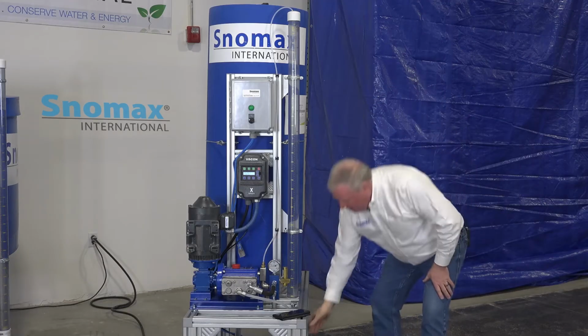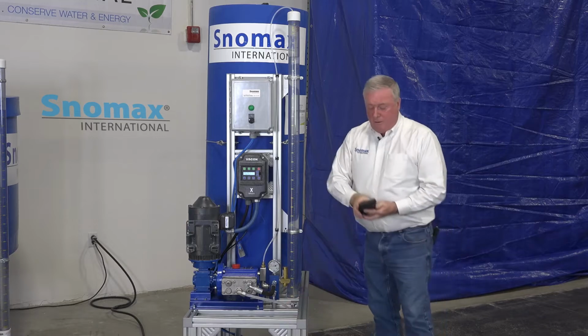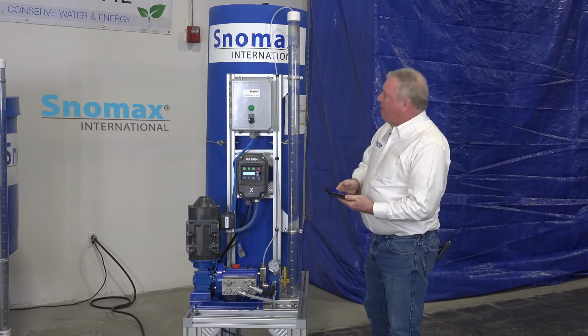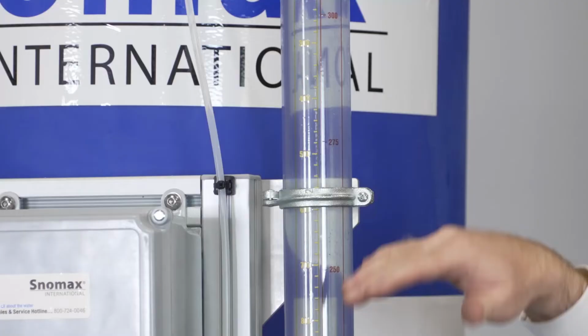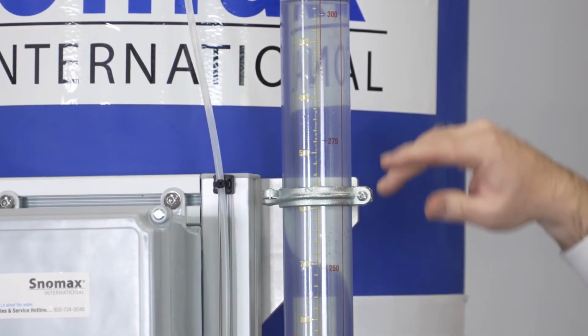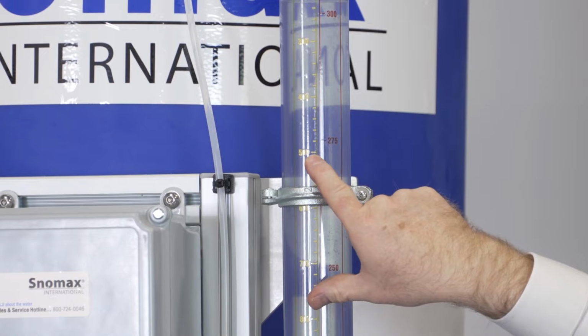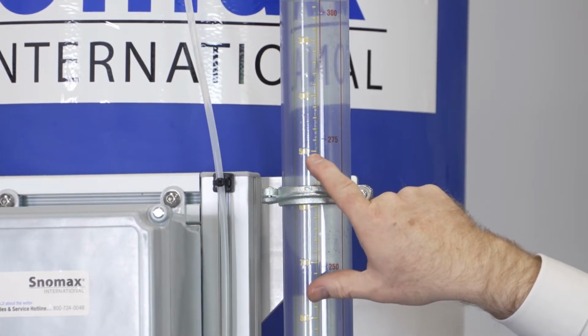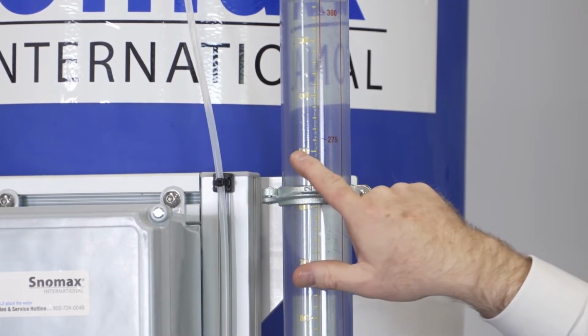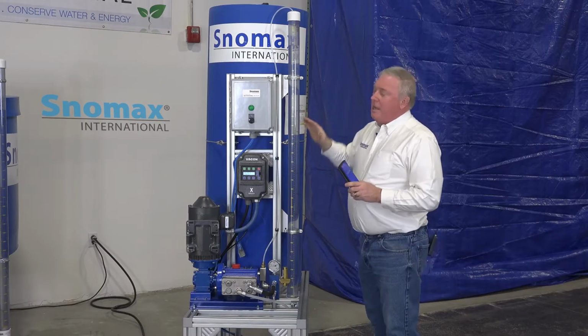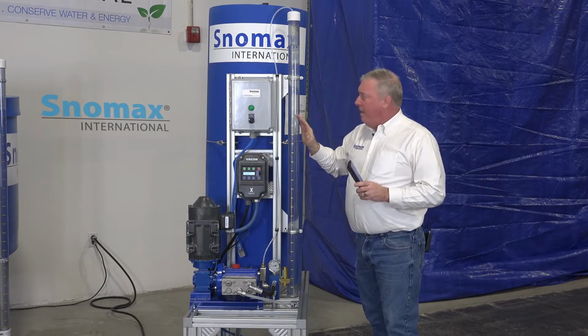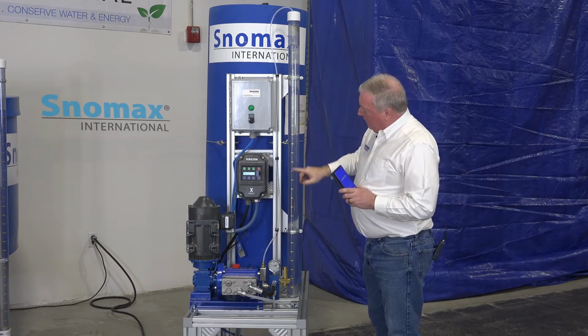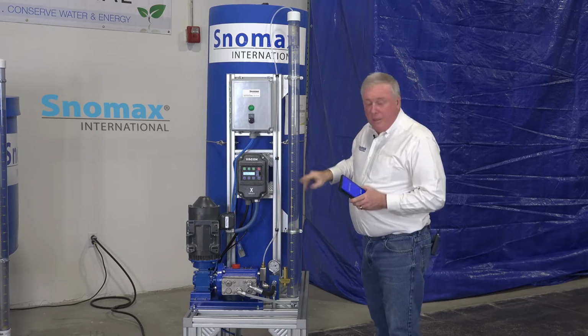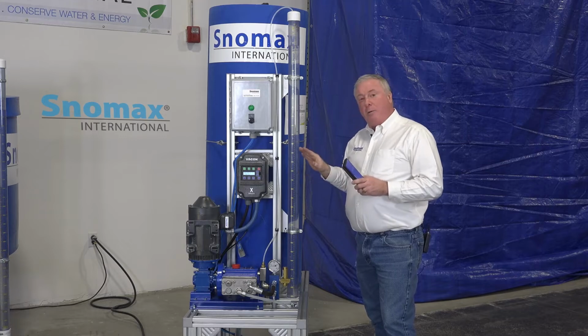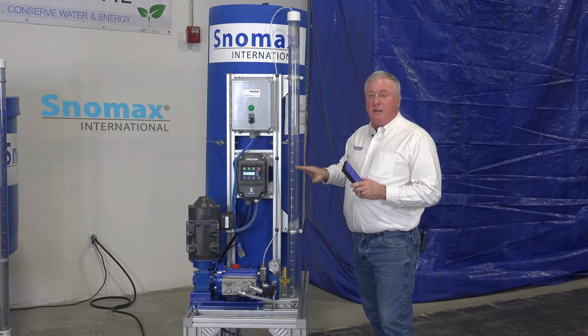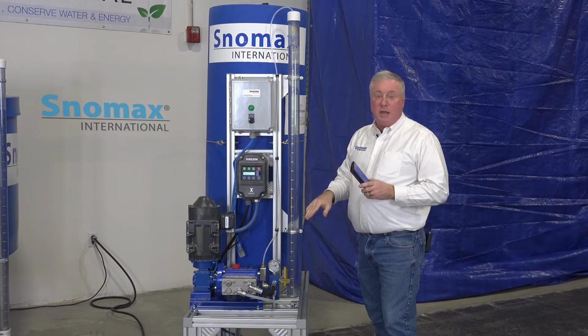So we're going to reset it, and then I'm going to use my phone to time it. I like to use round numbers that are easy to remember in your head, so I'm not even going to start timing until we get to 500 milliliters on this graduated cylinder. The reason is that today I'm saying you're going to be pumping 1,000 gallons a minute, so I'm going to want to go all the way down to 1,500 in 1 minute. And depending on whether we get there too soon or not soon enough, that'll tell us that we need to speed up or slow down the pump.